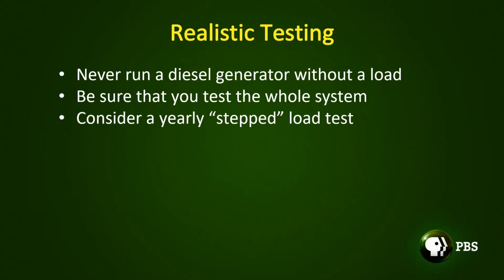What does that do? Well, it's like running your standby transmitter into an emergency load. It actually forces the whole system to perform under load. And it is one of the quickest ways to root out pending diesel engine problems. And that's, once again, if you go to the expense of having a full emergency power system, knowing that it's going to work is awfully important, or more importantly, knowing when it's headed for a failure.